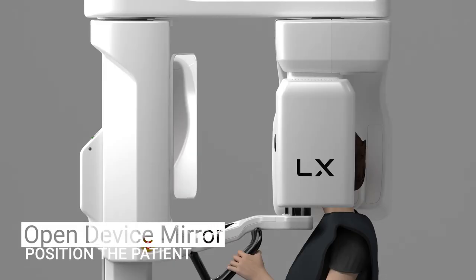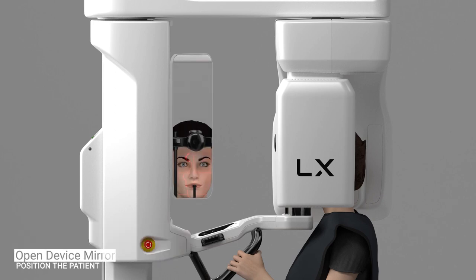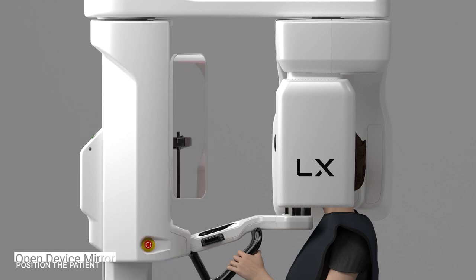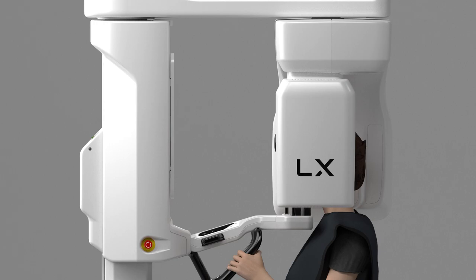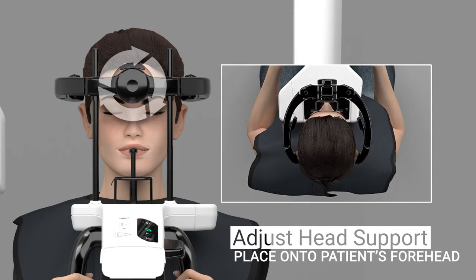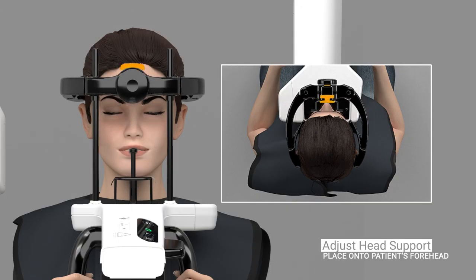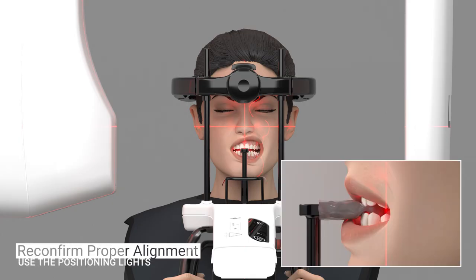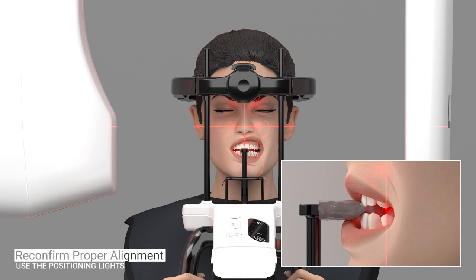You can open the mirror and use it to assist in positioning the patient. Close the mirror before you start acquiring an image. Close the head support by rotating the knob clockwise. Adjust the forehead support so it is resting against the patient's forehead. Reconfirm proper patient alignment using the positioning lights.